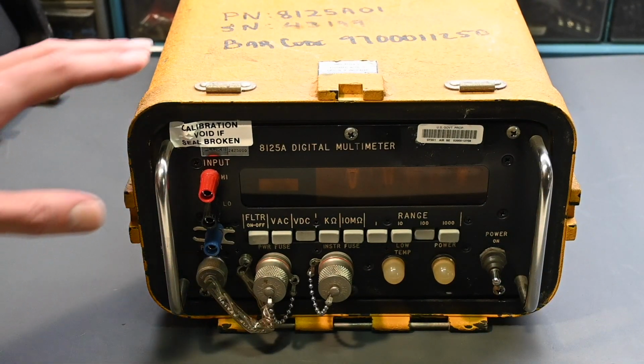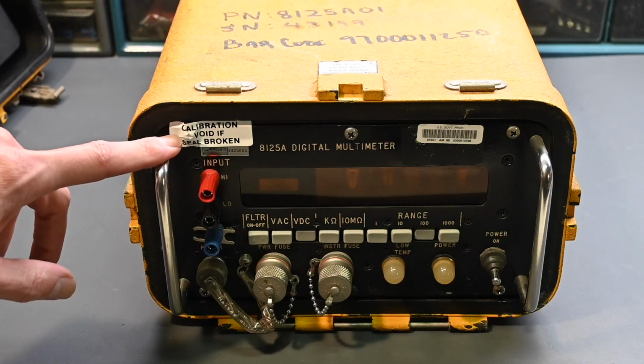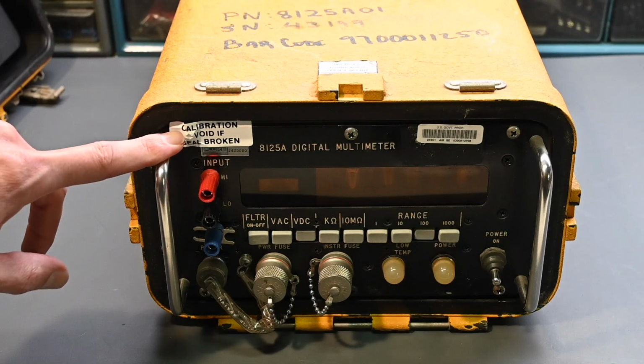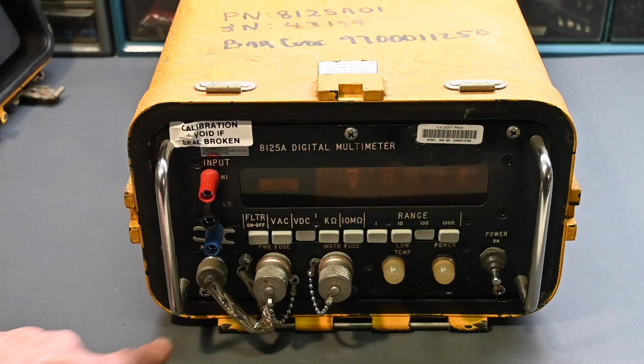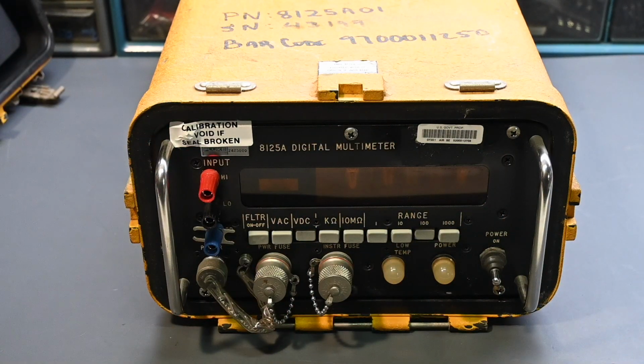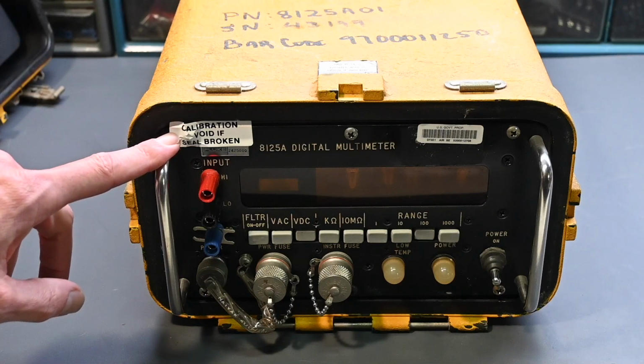One of the first things we notice looking at the front panel is that there's a calibration sticker here that's not been broken, over the head of this screw. There's 3 screws across the top and 3 more on the bottom. You take those out and the whole instrument comes out of the transit case. So it's a very good sign that it has a calibration sticker that's not broken.